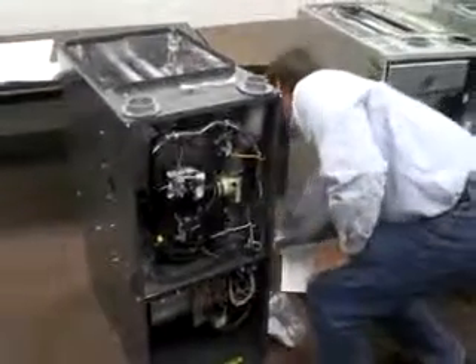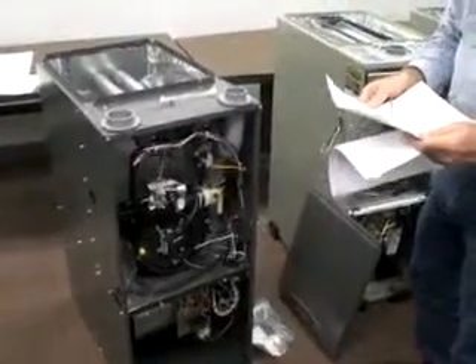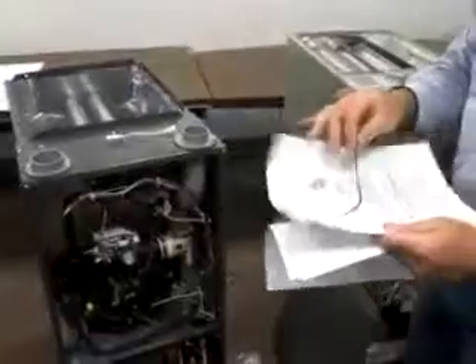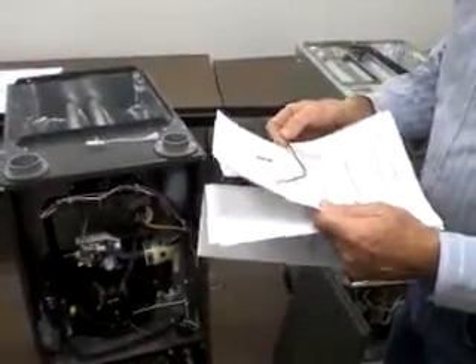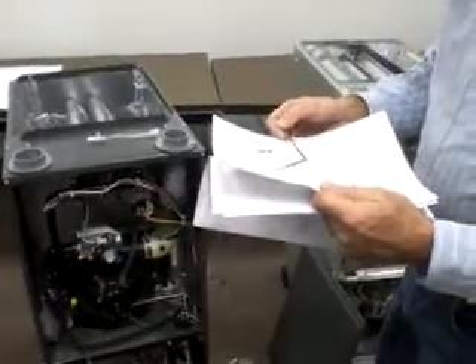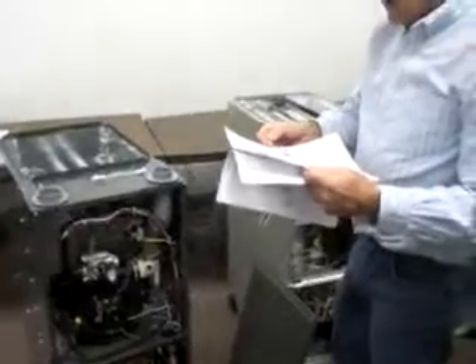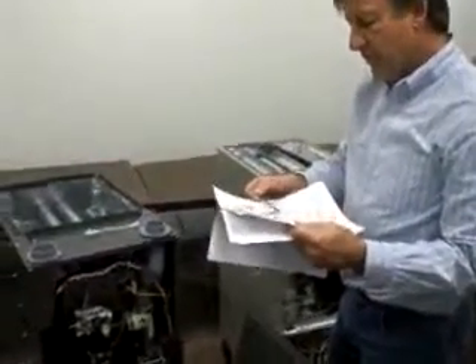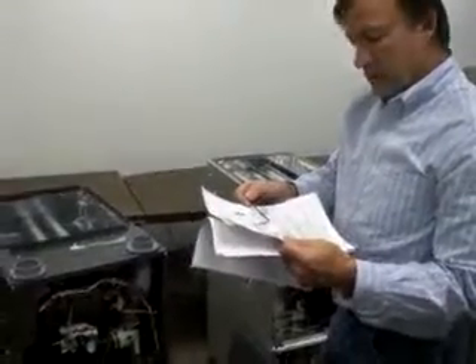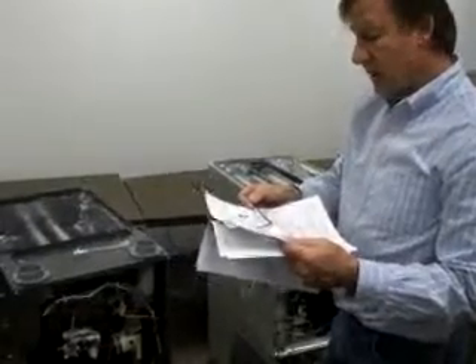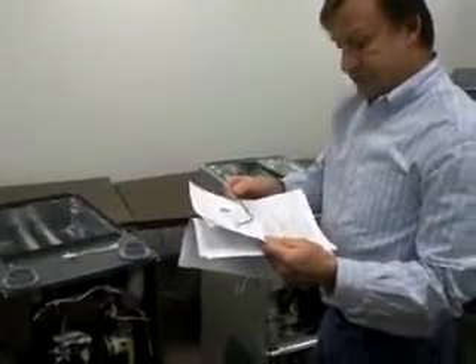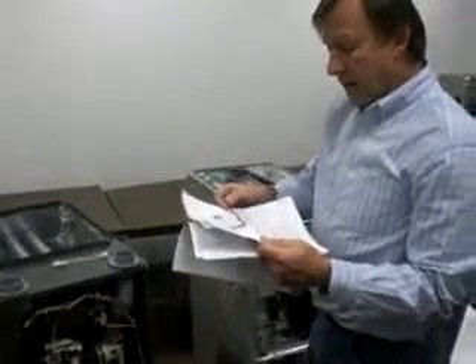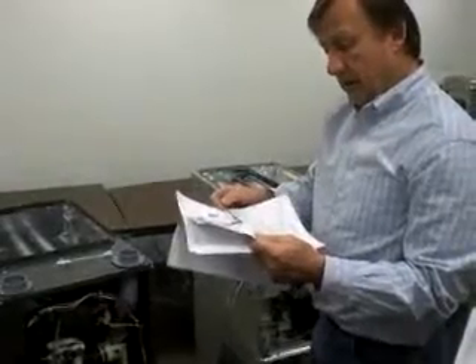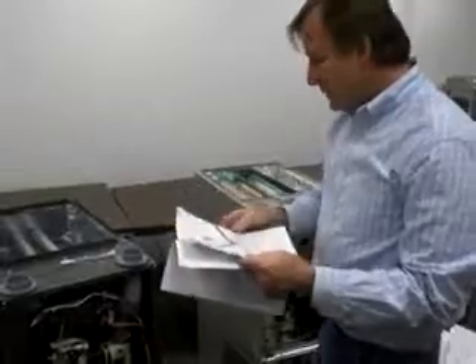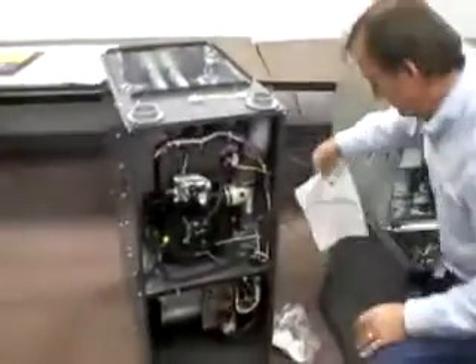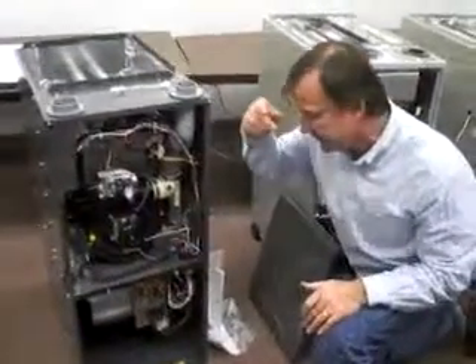They actually ship you a wire, and it's a pretty complicated procedure. It says the yellow wire connected to the ID blower pressure switch is powered whenever the pressure switch is closed and provides 24-volt humidifier control. Remove the yellow wire and connect the supplied brown jumper wire to the pressure switch terminal. Reconnect the yellow wire to the piggyback terminal on the brown jumper, and then connect the 24-volt line of the humidifier to the stripped end of the brown wire. This connection can be made using a wire nut or by using field-supplied quick connect terminal. The wiring must conform to all local and national codes. So on. Just another inconvenient way of adapting the unit to a normal application.